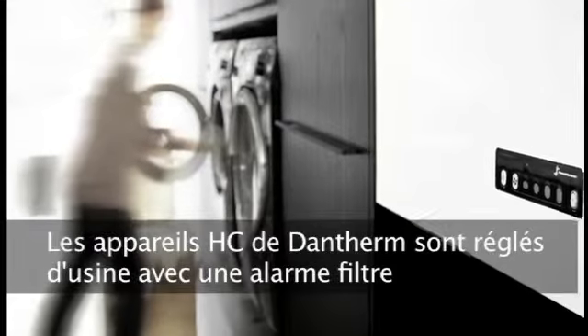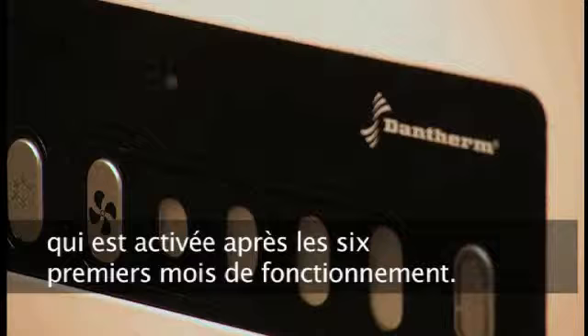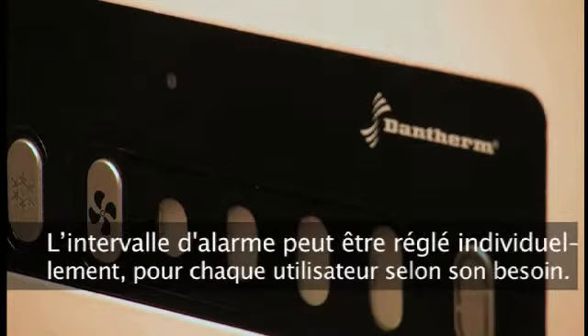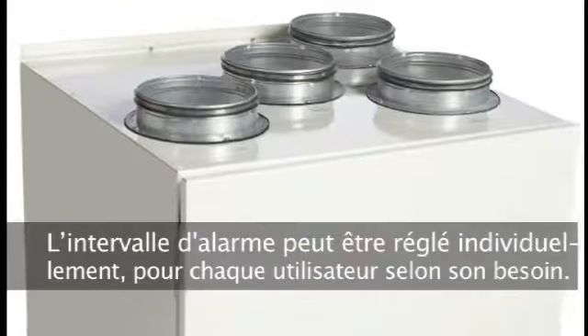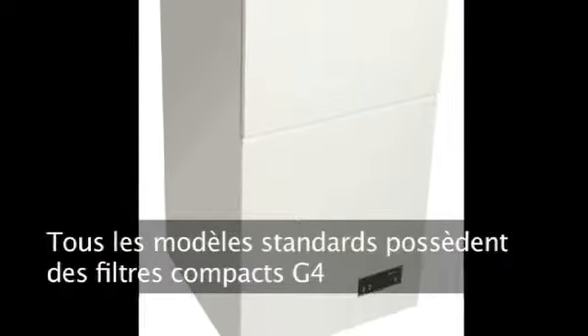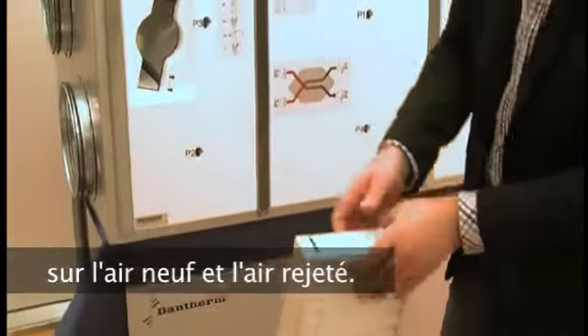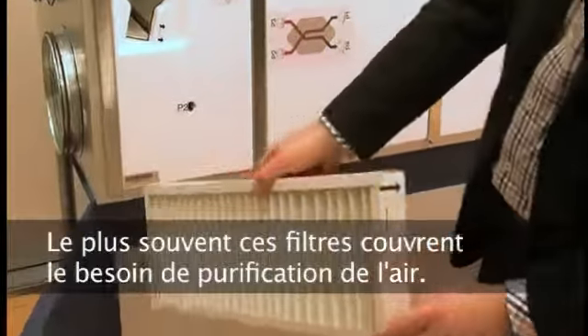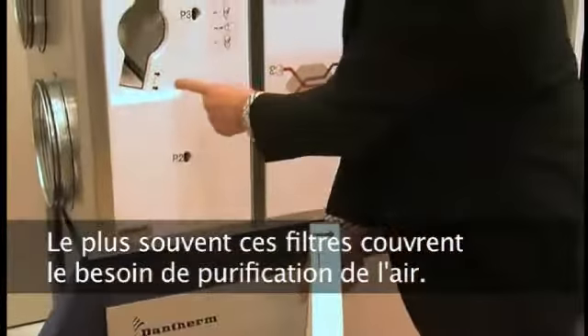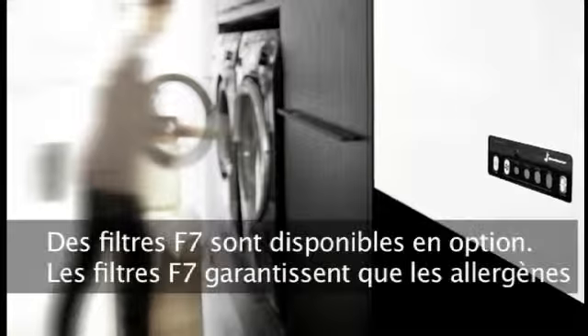Dantherm HC units are factory set with a filter alarm after the first 6 months of operation. The alarm rate can be set individually for each user's needs. All units have G4 compact filters as standard on both the supply air and the exhaust air. This will, in most cases, meet the demand for air purification. F7 filters are available as an accessory.